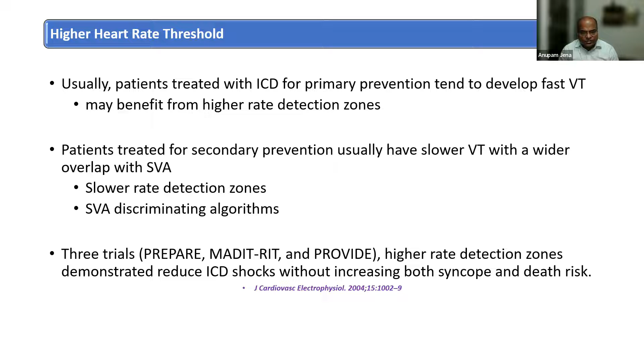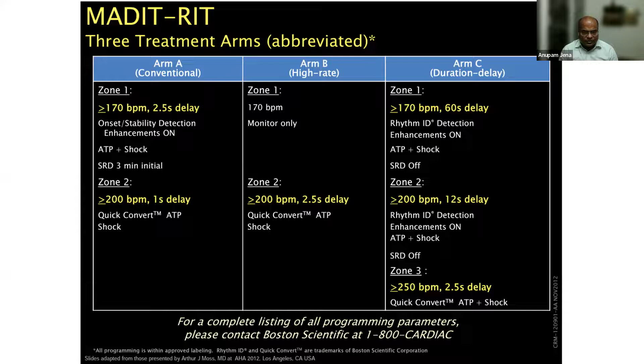All of us are aware of this, however, just for a quick reference, this was the MADIT-RIT protocol. This is the conventional arm, and in the high rate arm, up to 170, zone 1 is monitor only, there is no therapy, and zone 2, more than 200, has a 2.5 seconds delay, then ATP and shock. Zone 3 is arm C: at a rate of more than 170, the delay is 60 seconds before institution of therapy, and then the rhythm ID detection enhancements, ATP, shock. Zone 2, 200, has a delay of 12 seconds, whereas in the conventional programming, the delays are usually 6 seconds, 2.5 and 1 seconds. Here the detection delay is increased, and this was shown to reduce the number of shocks without increasing mortality or the number of syncope.